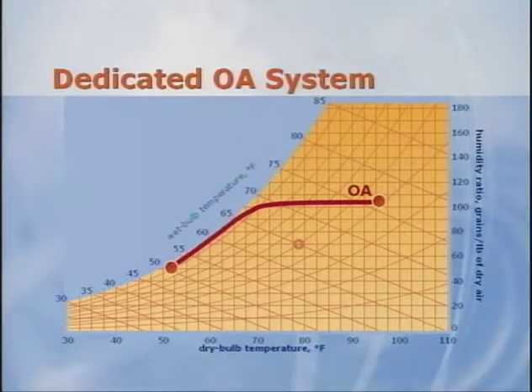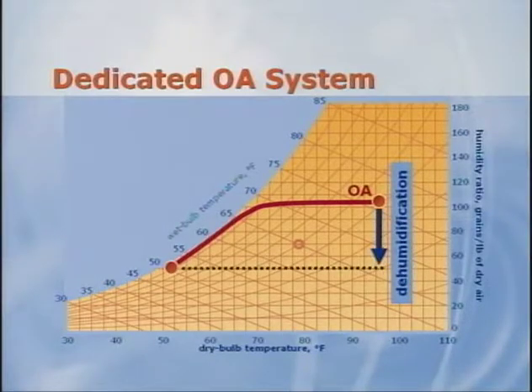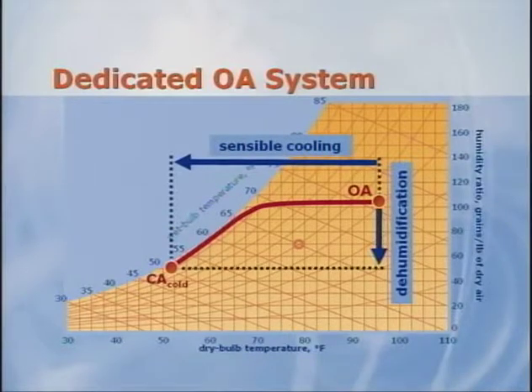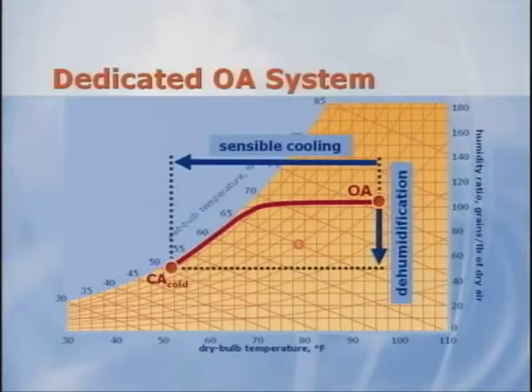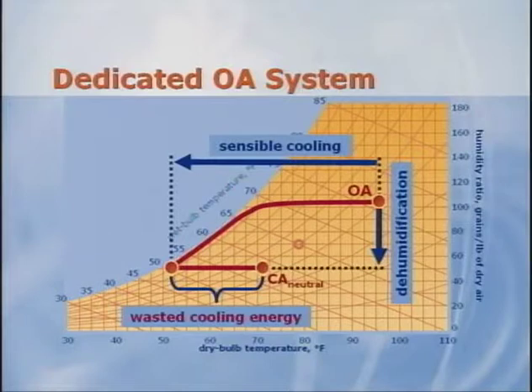When a chilled water or refrigerant coil is used to dehumidify the outdoor air, a byproduct of that dehumidification process is sensible cooling. The dry bulb temperature of the air leaving the coil is colder than the space. If the conditioned outdoor air is delivered at this cold temperature, rather than reheated to neutral, this cold air offsets some of the space-sensible cooling load. This allows the local fan coils to be smaller and use less energy. Plus, you avoid any energy used to reheat the air in the dedicated outdoor air unit. On the other hand, if this dehumidified air is then reheated to neutral, some of the sensible cooling performed by the dedicated outdoor unit is wasted, and that cooling must be done by the fan coils. Now, I talked about this topic in detail on last September's broadcast on dehumidification. So if you want more on this subject, you may want to view that broadcast.